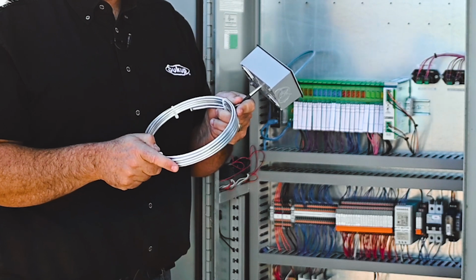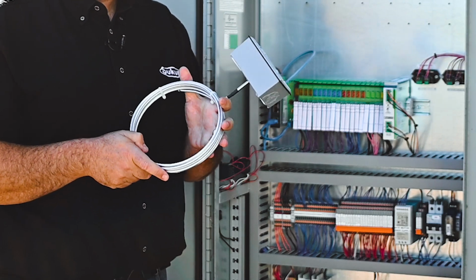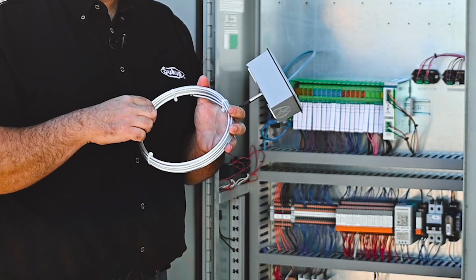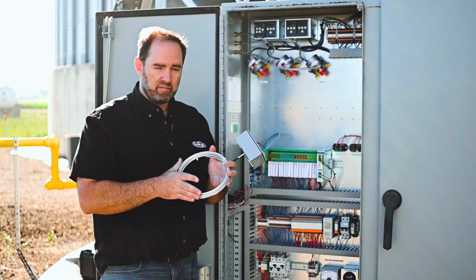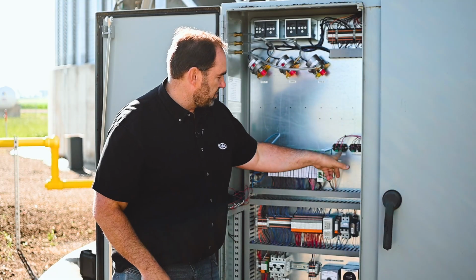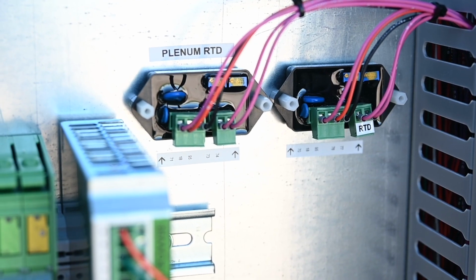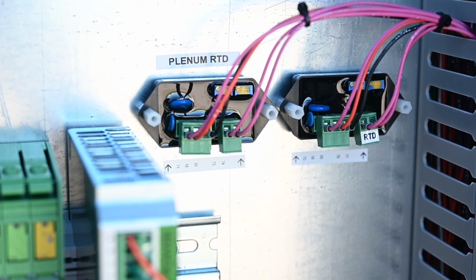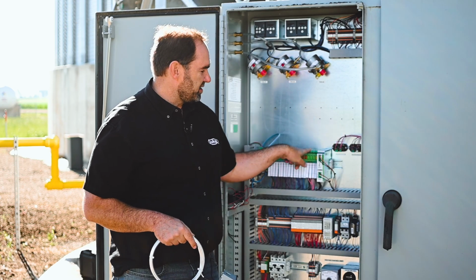And this will just give an average temperature, or really average resistance, along the entire length of this. So this is going to be the variable resistance. That is then fed into the plenum RTD transmitter on the 2-wire plug, where it's translated into a voltage, and then the voltage is fed into the PLC.